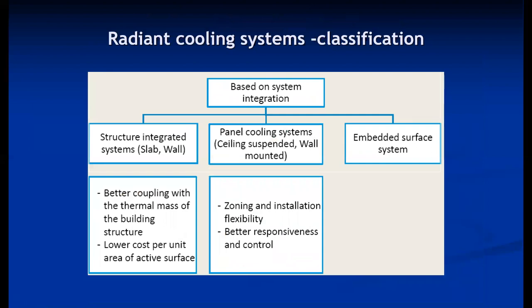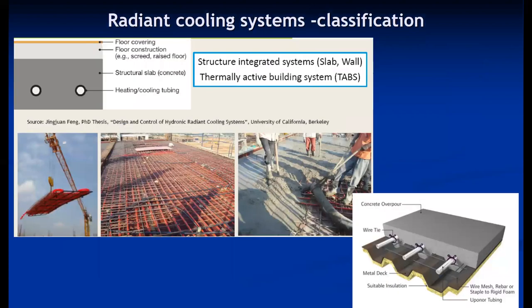There are different classifications based on the structure of radiant cooling systems: structure-integrated systems, which are fitted integral with the slab and wall; panel cooling systems; and embedded surface systems. Structure-integrated systems provide better coupling with the thermal mass of the building and are comparatively low cost per unit area. Panel systems offer proper zoning, installation flexibility, better responsiveness, and control.